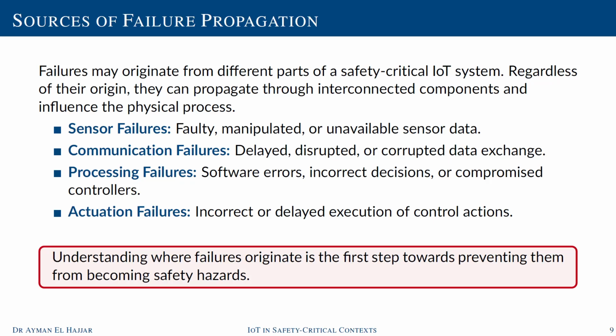and so on. And processing failures occur when software errors, compromised controllers, incorrect algorithms, or faulty decision logic produce the wrong output. Actuation failures occur when control actions are incorrect, delayed, repeated, or not executed at all. This is the point where cyber and software failure can become physical actions. Understanding where the failure originates is the first step towards preventing them from becoming safety hazards.